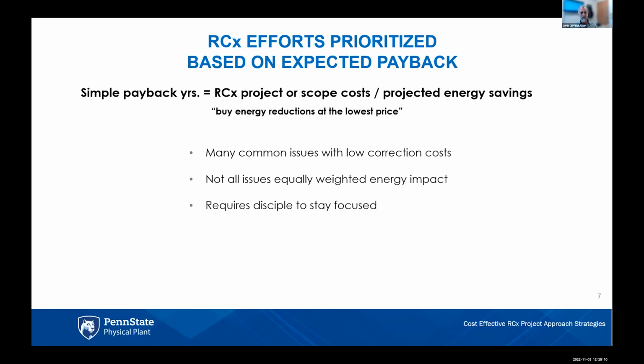Fortunately, there are many common issues that can be corrected at very low cost, and those typically will be through the BAS control system parameters, logic, things like that. And not all the issues are weighted equally as far as energy impact. I'm much more interested in a fault with a 50 horsepower supply fan in an air handler than I am with a 3 horsepower hot water distribution pump. And then there's the discipline to stay focused, because invariably when you're commissioning, you can see low priority things that might kind of bug you, like a bad graphic or some other thing. So we document those things and try to move on if we're going to stay on target to meet our goals.